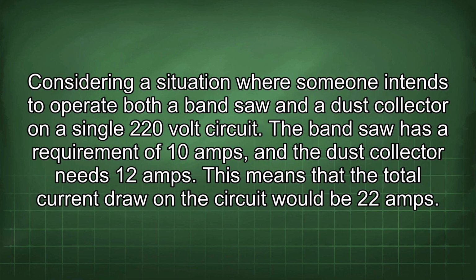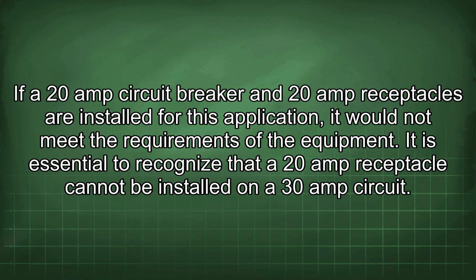Consider a situation where someone intends to operate both a bandsaw and a dust collector on a single 220-volt circuit. The bandsaw requires 10 amps, and the dust collector needs 12 amps. This means the total current draw on the circuit would be 22 amps. If a 20-amp circuit breaker and 20-amp receptacles are installed for this application, it would not meet the requirements of the equipment. It is essential to recognize that a 20-amp receptacle cannot be installed on a 30-amp circuit.